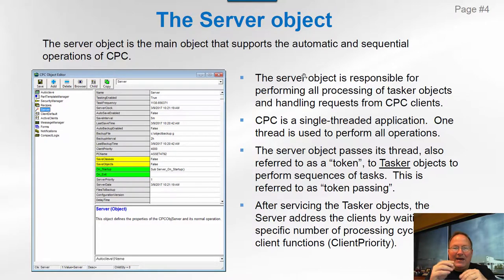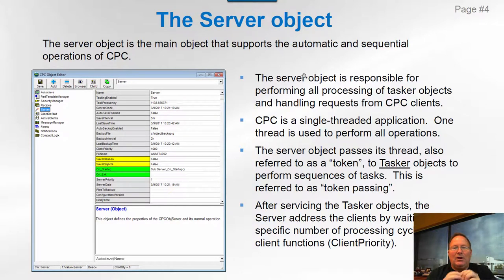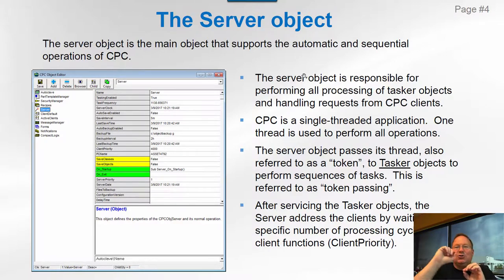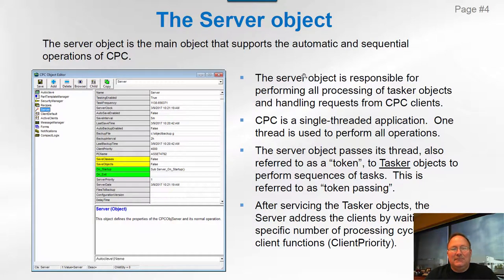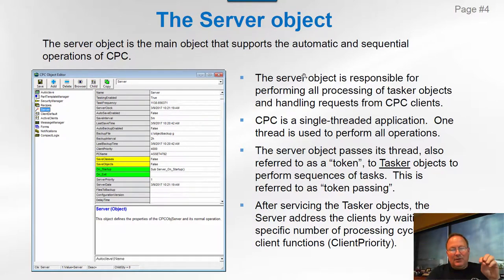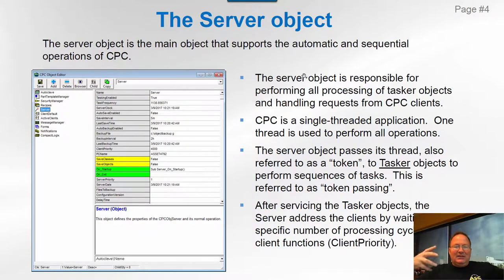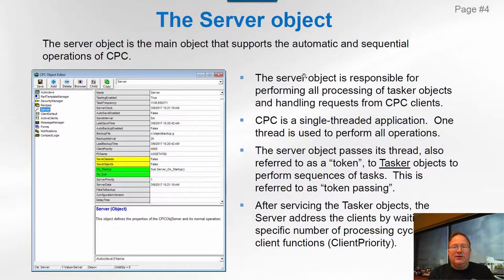The reason we use one thread and not multiple threads is that we want all the clients to be looking at the same data in the object structure — multiple threads can't do that. The server object passes its processing thread to other users. One such user is the tasker object, which does the sequencing of control. When the server passes that execution thread to a tasker, we call it a token, and when you pass it, it's considered token passing.